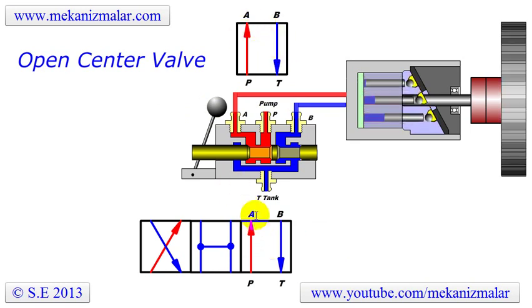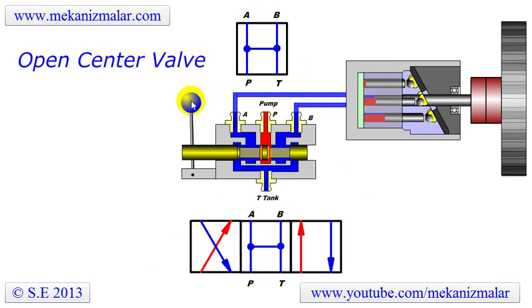Note that in this case the rotation direction of the motor is reversed. The corresponding flow diagram representing the extreme right position is shown by a square diagram at the top. In the center position of the valve, all ports are connected to the tank port T, which relieves the pressure from ports A and B.